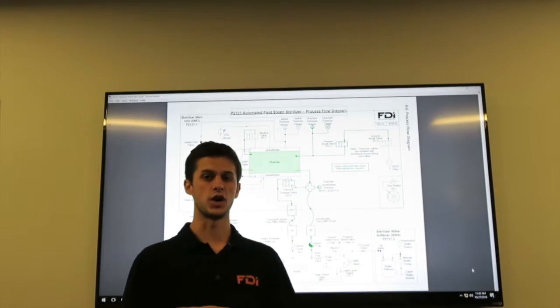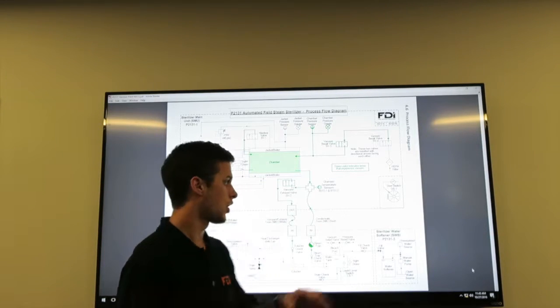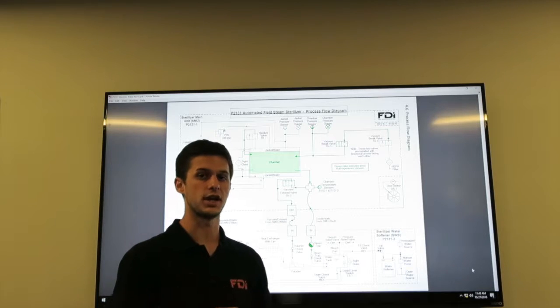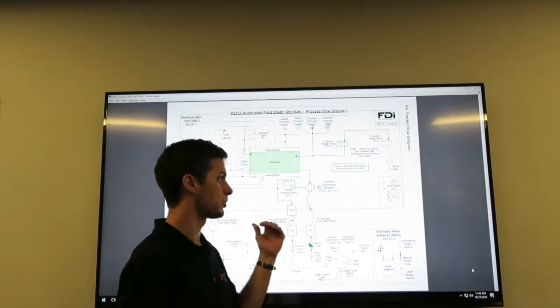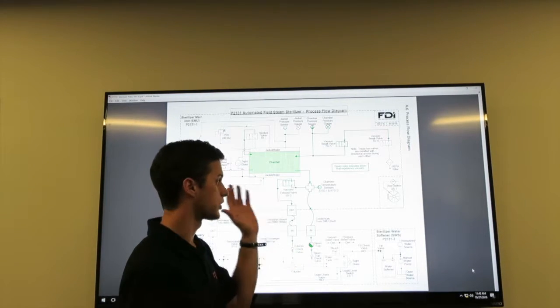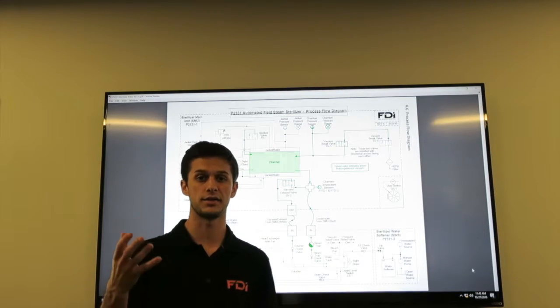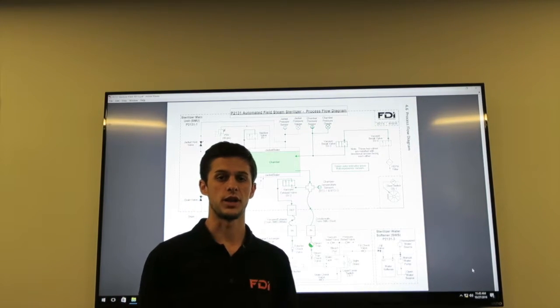Kind of just some big picture overview of it. All the little details will help you visualize the sterilizer and help you troubleshoot. If something's going wrong, you can reference the process flow diagram. It's at the back of the technical manual and it'll help you troubleshoot.